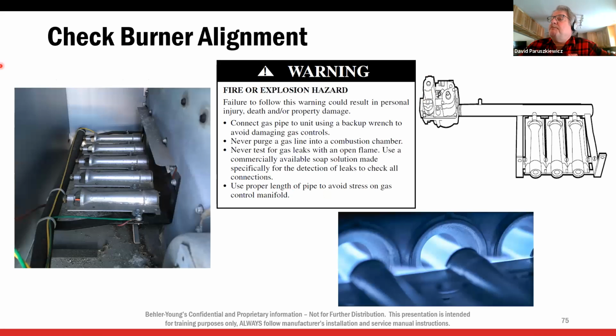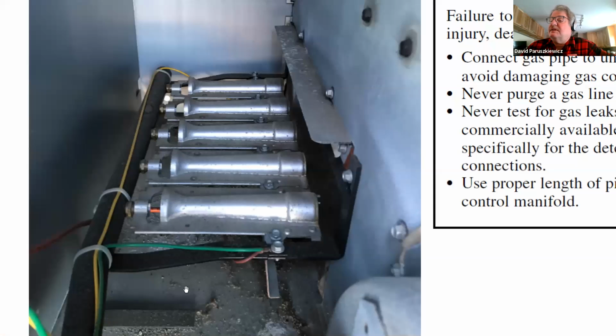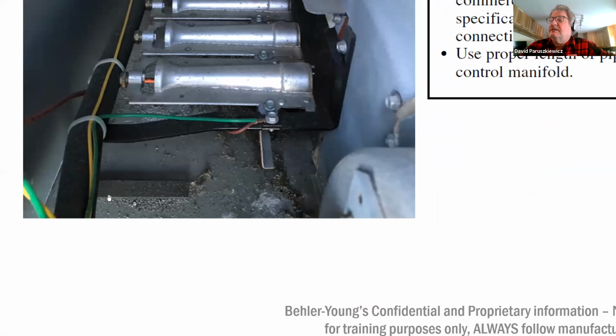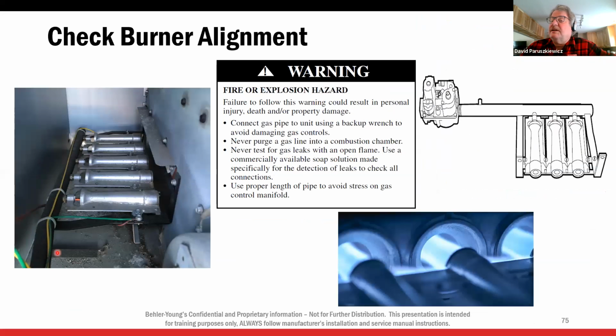Okay, burner alignment. Now, this is a problem we see, and it's pretty simple. Here you can see is a burner, and you see this little bar down here. Hopefully you can see where my little laser pointer is. That little foot should be down on the bottom of the unit.